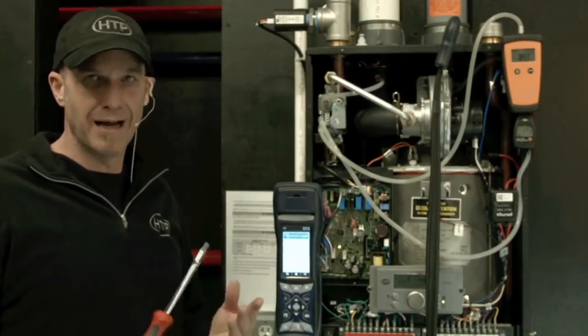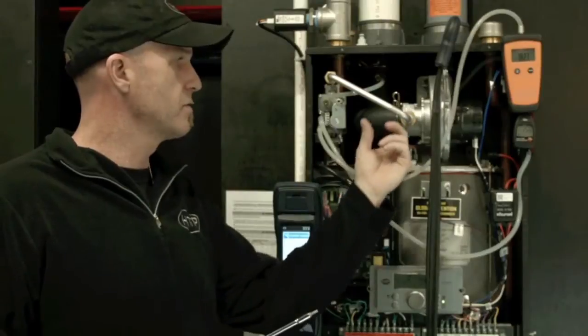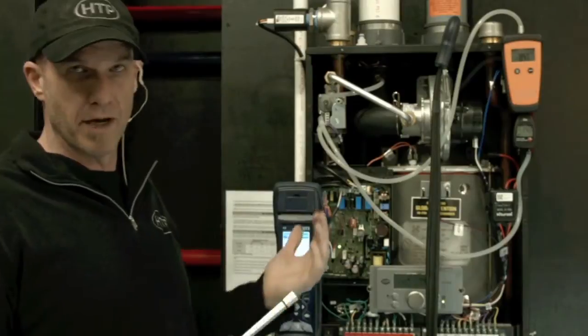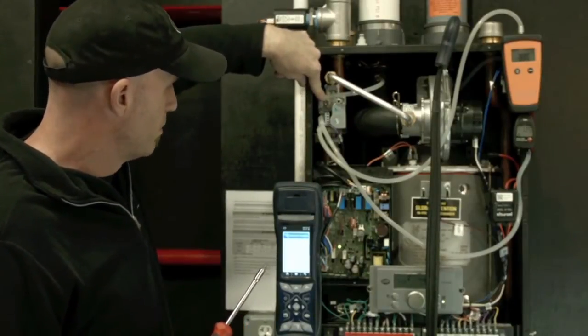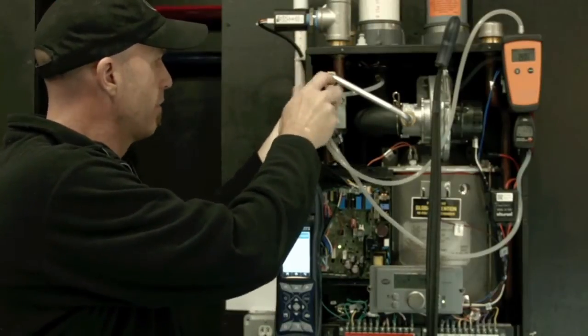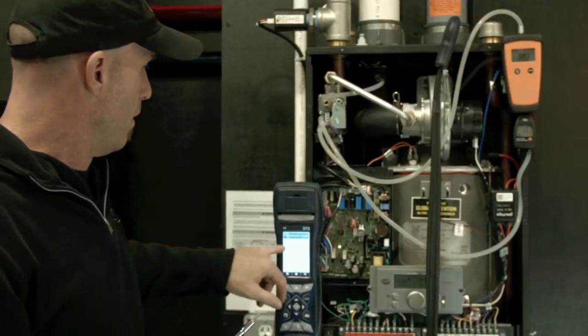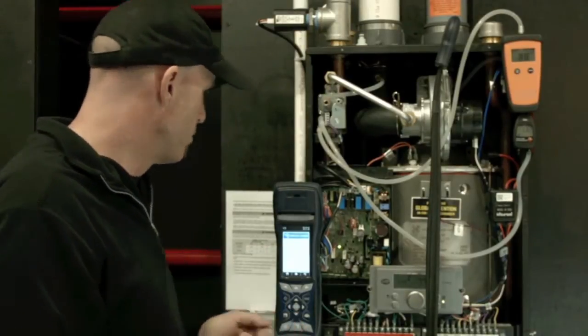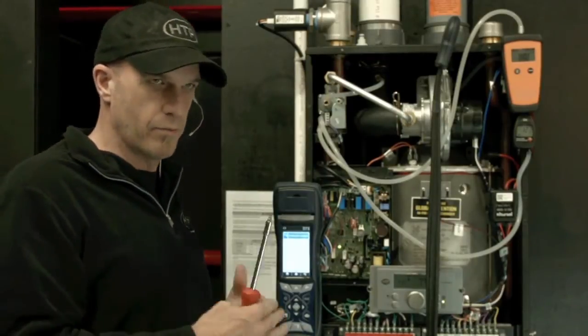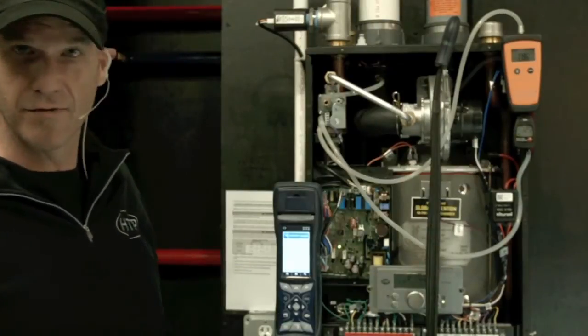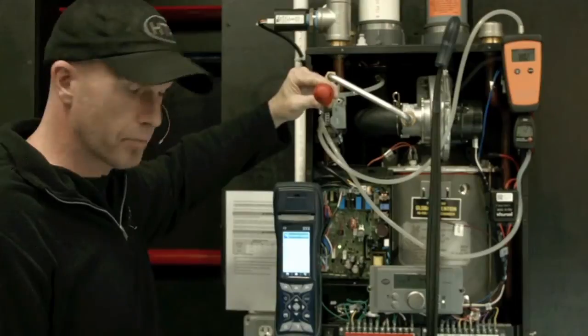So when we make the adjustments, you're going to need to have a 4mm Allen key to make the adjustment on this valve. This is a single orifice valve, so it has no throttle or internal throttle adjustment. High-Fire is done with a gas orifice, whether it's propane or natural. So we're going to be focused on the low side or the manifold pressure or offset. So on this particular valve, the offset adjustment or the adjustment that we're going to use is right here. So what you're seeing here is a cap. So we're going to get this cap out of our way, and again, it's still the same 4mm cap. Just sort of puts the adjustment away for you. So what I can see here is on my CO2, we're sitting at about 5.2%, which of course is very low, and my CO is rising. So what this is telling me is that we're having a real hard time burning all the fuel off of there. The outlet pressure is definitely a little bit too far off. So we can see it's real far negative here, so it's very lean. So I'm going to slowly start to go a little bit clockwise on this valve and add a little fuel and see if I can bring that CO2 number up and in the process bring my CO down.